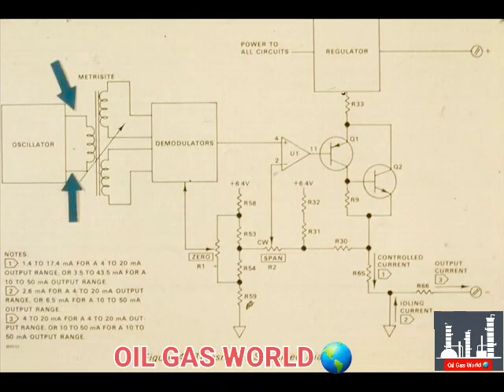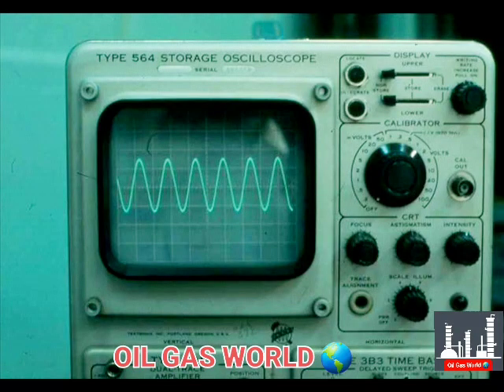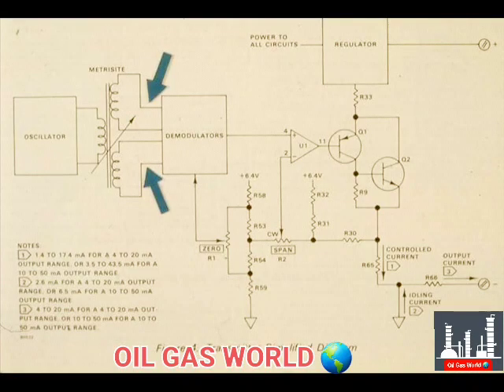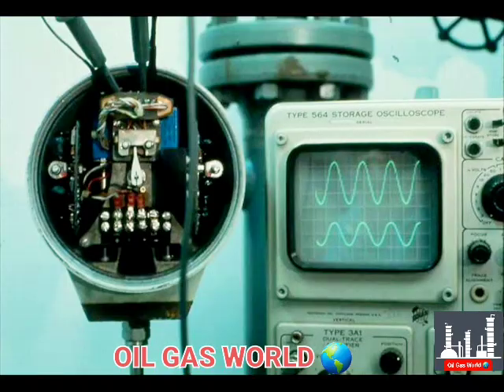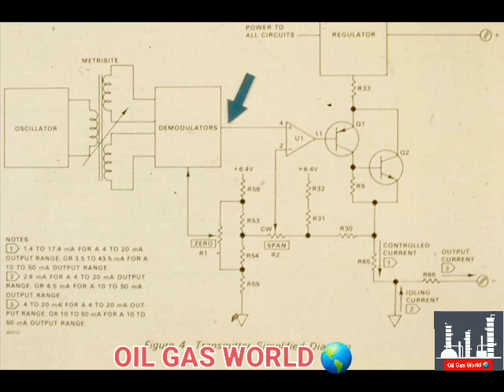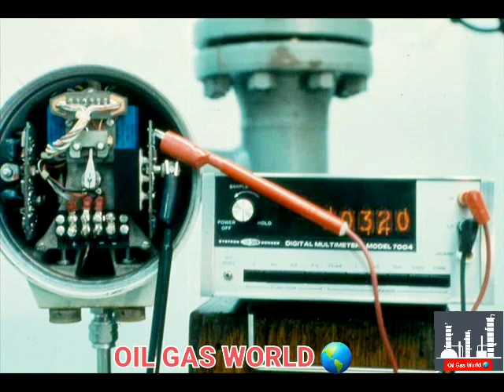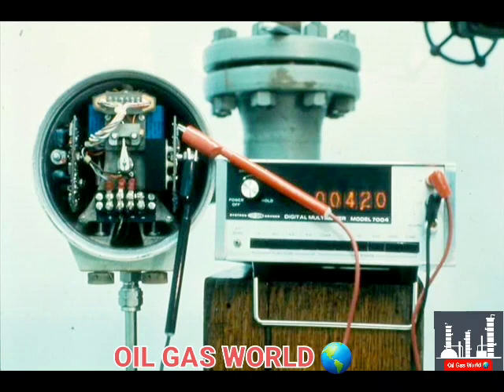Now we will look at the simplified diagram and make voltage measurements to further understand the operation of the device. Here is where we would measure the oscillator output voltage — here you see the waveform. To measure the Metrisite secondary voltages, attach inputs here. Attach a DVM from the demodulator output to ground to observe its operation. This is the demodulator output with zero percent level, and this is the demodulator output with 100 percent level.